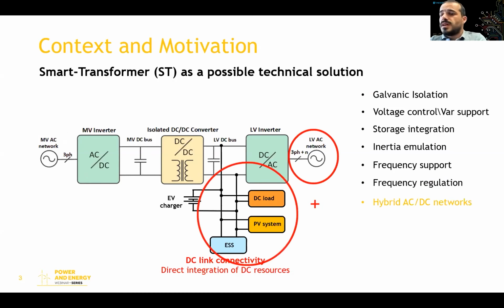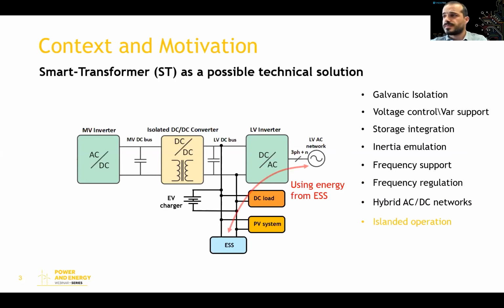And of course, it can integrate hybrid AC/DC networks, which is arguably one of the most important features of the smart transformer. It is possible because the smart transformer offers DC connectivity, which can be very useful to integrate DC resources directly. And finally, I have here the islanding operation. Since the smart transformer can integrate storage, it can operate its own distribution network in island mode in case of outage of the upstream power system.